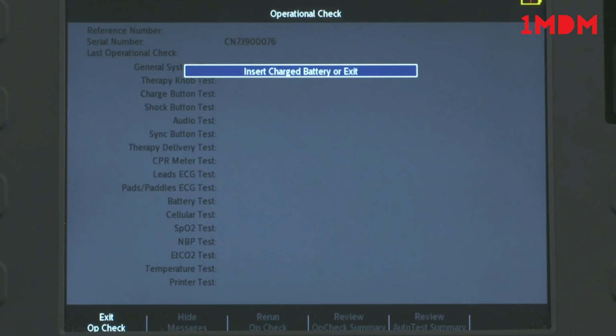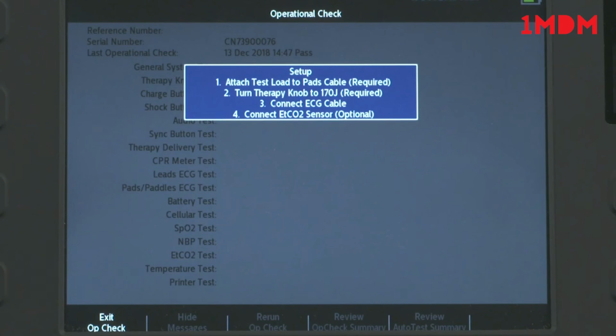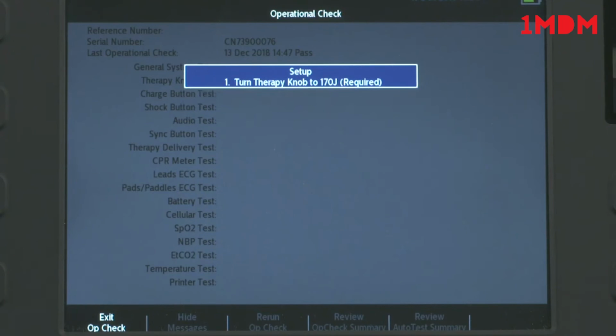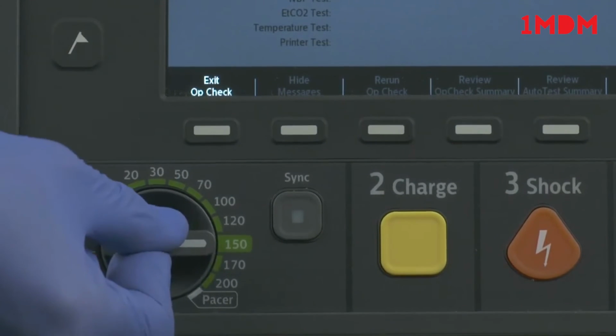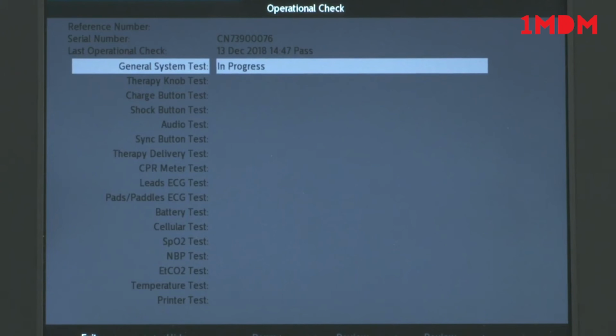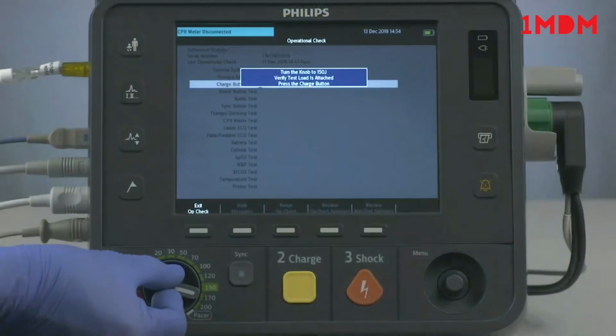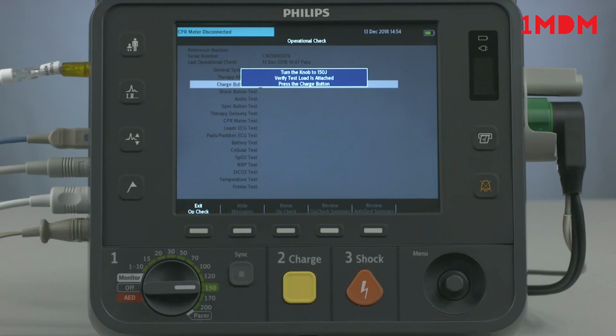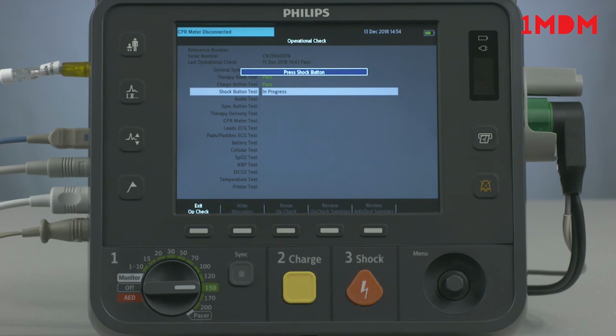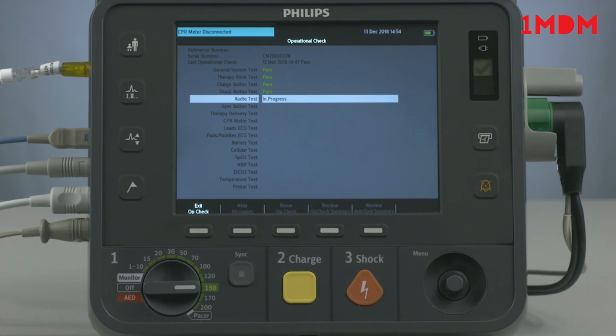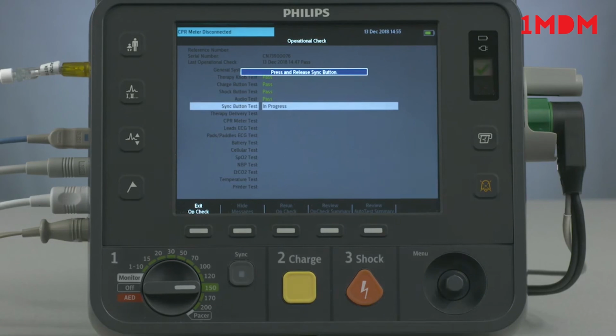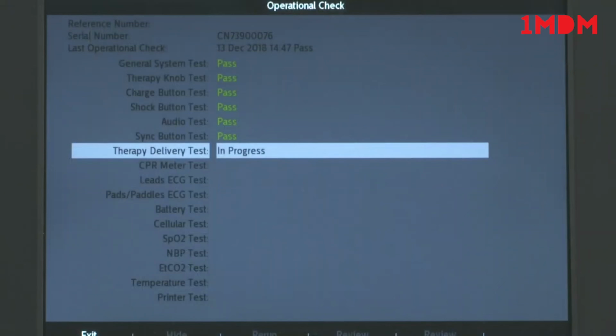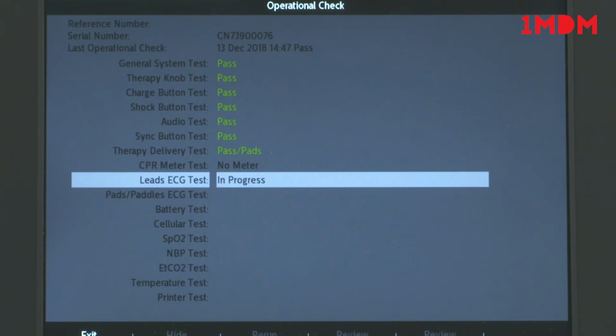Confirm your device has a charged battery and an ECG cable connected. You will be prompted to set the therapy knob to 170 joules. You will then be prompted to set the therapy knob to 150 joules. If everything is set up as expected, the series of tests will begin with a few interactions along the way. If not, you will be prompted to correct the setup, proceed with the test based on the current setup, or exit op check. As each test is run, the message window In Progress displays. You are given a pass or fail indication upon completion of each test.